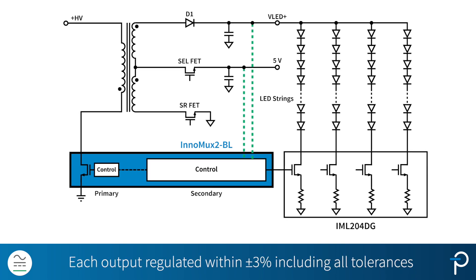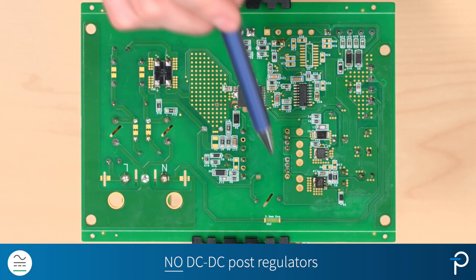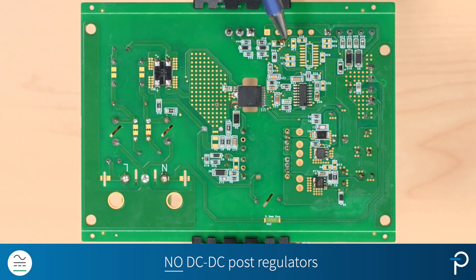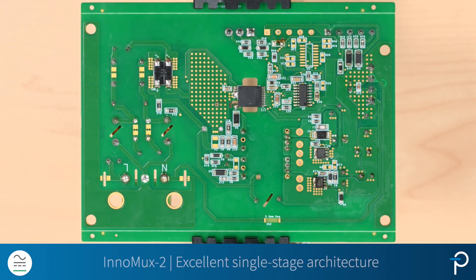By doing so, the regulation on each output is within plus or minus 3%, including all tolerances. As you can see, there are no DC-to-DC regulators on the board. The system can deliver over 89% efficiency at full load condition from end to end — this is all because of InnoMux-2's excellent single-stage architecture. To learn more about InnoMux-2, please visit power.com.